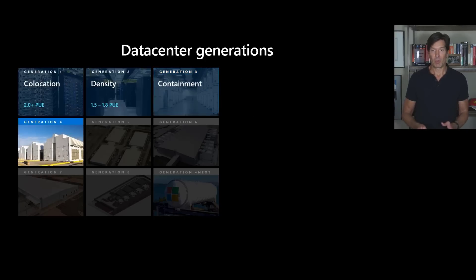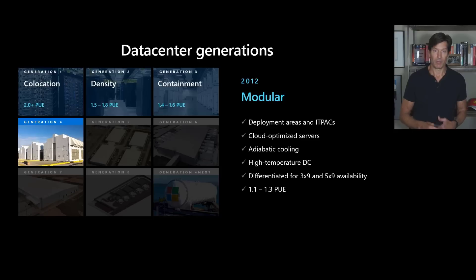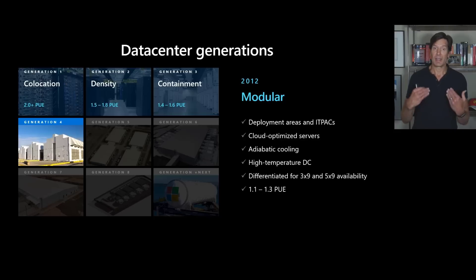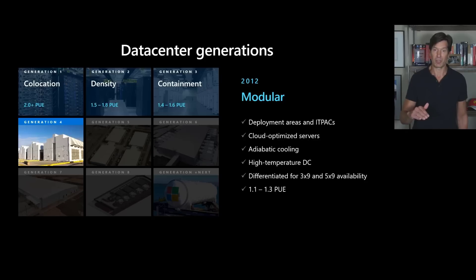In generation four, we moved away from containers — which we found were actually more expensive for long-term maintenance — to an ITPAC approach, where we pre-deploy areas on the data center footprint for certain types of servers, with network cabling and everything else pre-configured. We also switched to adiabatic cooling, meaning we use the ambient air temperature around the data center to lower cooling costs, and we could operate servers at a higher temperature. This allowed us to get PUEs down to between 1.1 and 1.3.